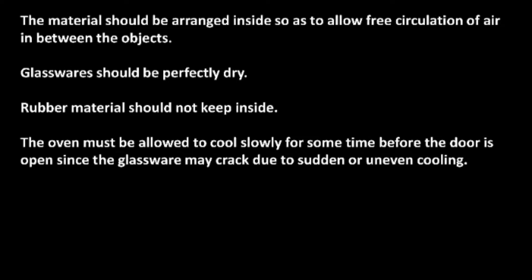Materials should be arranged inside to allow free circulation of air between objects. Glassware should be perfectly dry, and rubber materials should not be kept inside. The oven must be allowed to cool slowly before the door is opened, since glassware may crack due to sudden or uneven cooling.